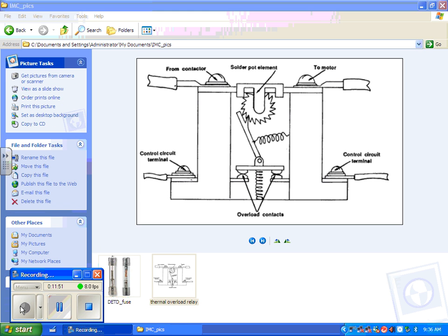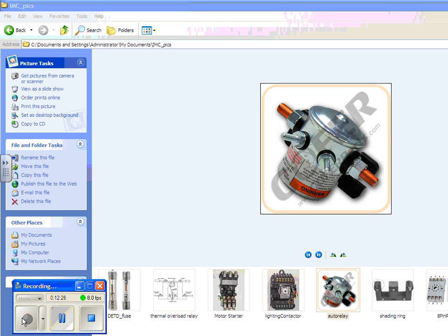All right, so this is the overload device, solder pot overload device, same one that's on page 37 or whatever page that is. And I want to go on to talk about solenoids, relays, contactors, and motor starters. Those are all different things. All of them are electromagnetically operated. Okay, when we start talking about relays, lighting relays, solenoids, contactors, motor starters, they all have one thing in common, is that they're electromagnetically operated, and that because of that we can control them remotely.